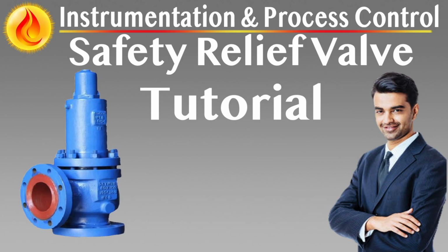Functional advantages. Soft seat sealing provides excellent leak tightness, reducing loss of process fluids and emissions. Compact size and lower weight compared to large spring-loaded valves at equivalent capacities. Set pressure accuracy remains stable even under significant pressure drop conditions between protected equipment and the relief inlet. Allows a closer approach to the system's MOP, optimizing equipment operation and reducing unnecessary relief events. Offers a higher positive closing force, minimizing the risk of chatter at low overpressure conditions.